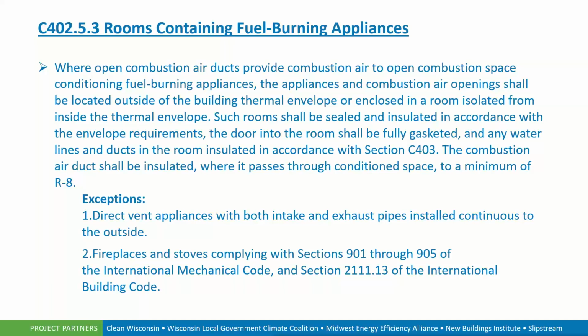that the doors are fully gasketed, and water lines of those areas are installed in accordance with section 403. Our combustion air ducts have to be insulated if they pass through a conditioned space, and so forth. So there are certain requirements when we have fuel burning appliances, say within mechanical closets. There are some exceptions, and different parts of the requirements apply to this point. And you can see there are some exceptions.